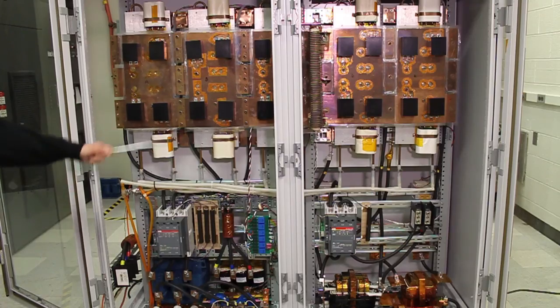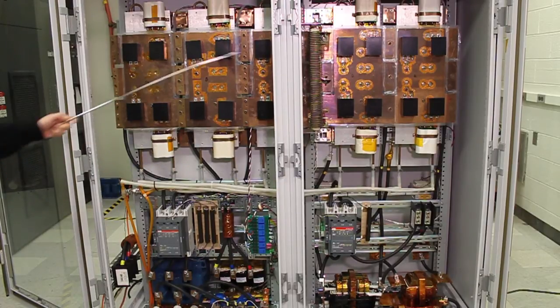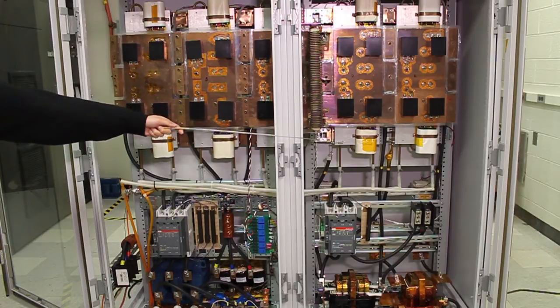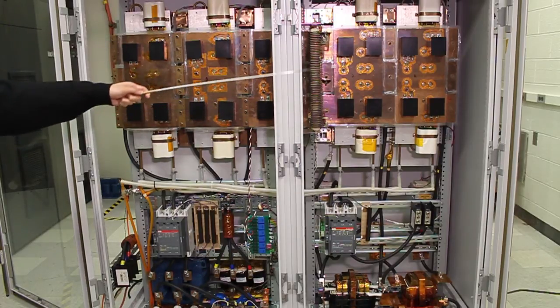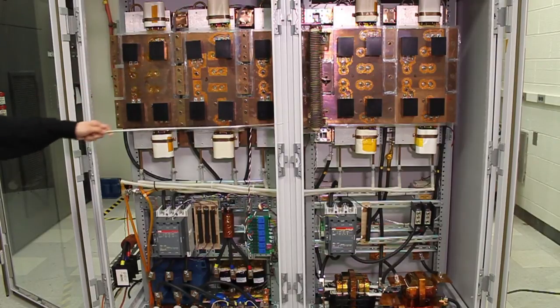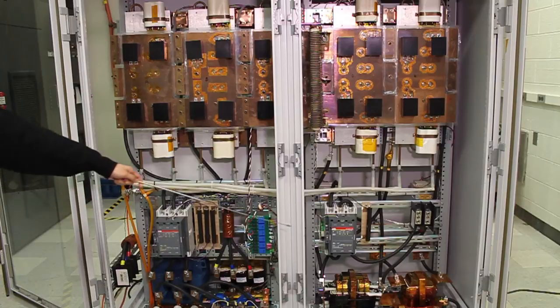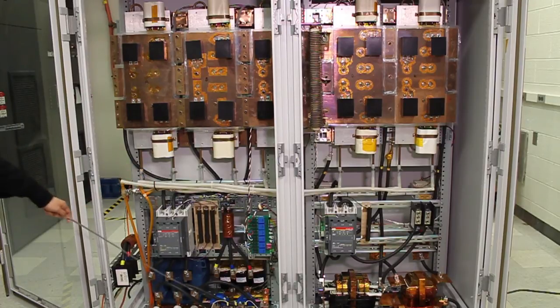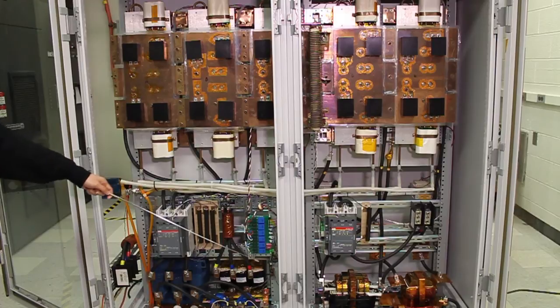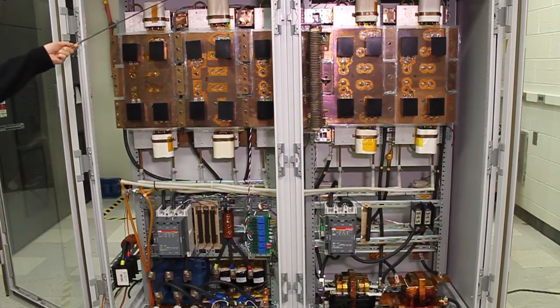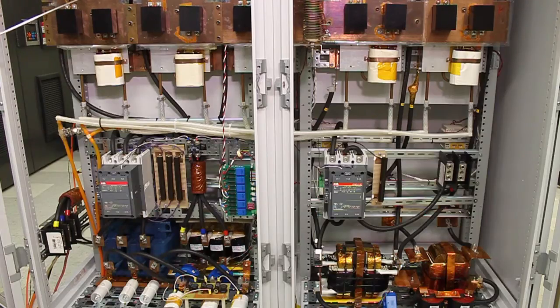Here is the 3-level NPC power conversion system hardware. The left-hand side of the cabinet contains the DC-AC inverter, and the right-hand side is the DC-DC chopper. The modularized phase-leg building blocks are mounted on the top part of the cabinet, and the auxiliary circuit and also some passive filters are mounted at the bottom of this cabinet, and the control card is mounted at the back of this cabinet. The DC-AC power stage contains 3 of these phase-leg building blocks and a customized LCL filters.